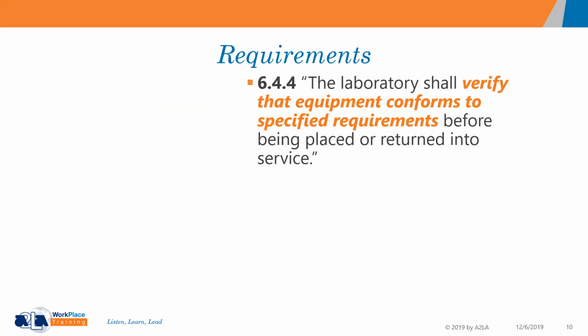So, looking at the requirements of 6.4.4, the next nonconformance. The laboratory shall verify that its equipment conforms to specified requirements before being placed into service. As I mentioned in the previous comment, there is no requirement in the standard for what verification is. It gives you the latitude to go in and determine what that is based upon the risk you're willing to take by the rigor that you put into this.